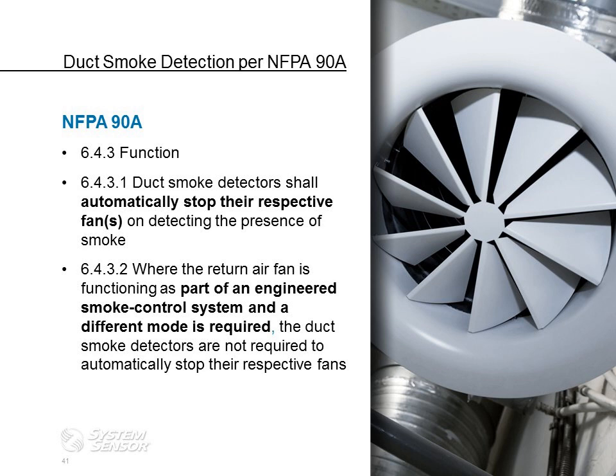NFPA goes on and talks about the function of the duct detector, what it's supposed to do. Duct smoke detectors shall automatically stop their respective fan or fans on detecting the presence of smoke. Again, we want to stop the transference of harmful materials from one section of a building to another. Where the return air fan is functioning as part of an engineered smoke control system and a different mode is required, the duct smoke detectors are not required to automatically stop their respective fans. That's important to know for your knowledge.